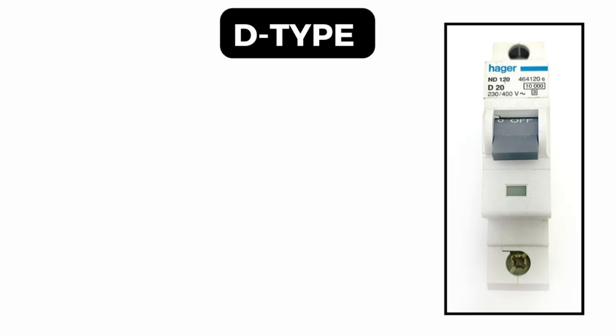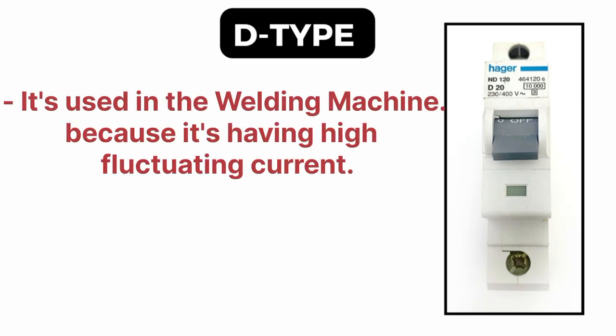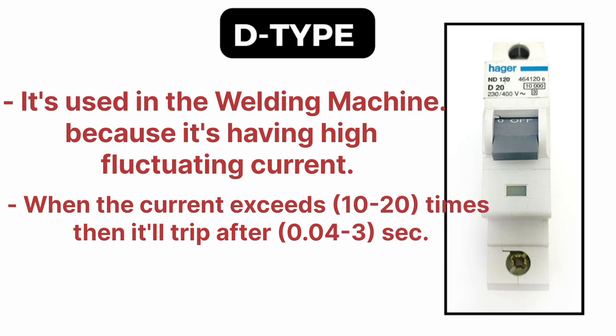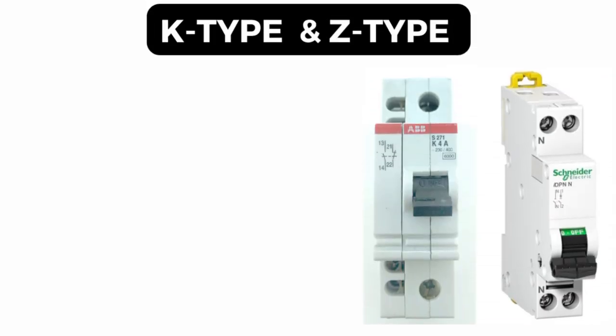Type D MCB is basically used for welding machines, because welding machines have very high fluctuating current. Type D MCBs are used for high fluctuating current devices. The current tripping capacity is 10 to 20 times the rating, and the required time for tripping is 0.04 to 3 seconds.